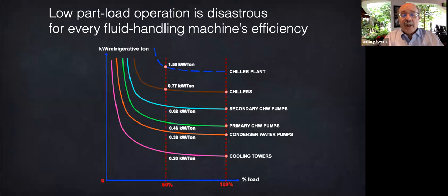A motor without an ASD is like an internal combustion engine car without a transmission. It'll work well in a narrow speed range, but it'll struggle or stall at other speeds. But a pumping system with a throttling valve is like driving with the accelerator always floored and controlling speed with the brake. Actually, it's worse than that because the pump's power varies as the cube of its flow.